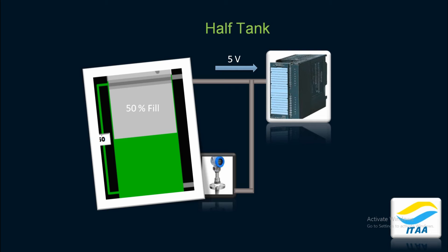If the level is now 50%, what will be the value going towards the input card of the PLC? That will be 5V — because 5 is exactly half of 10, and 50% is exactly half of 100%. So it will be 5V going to the PLC, and the PLC will understand that 5V means 50% filled in the oil tank. For 100% full, the signal from the transmitter to the input card of the PLC will be 10V, because 10V is the maximum. So according to the varying level, a signal in the range of 0–10V is sent to the PLC.